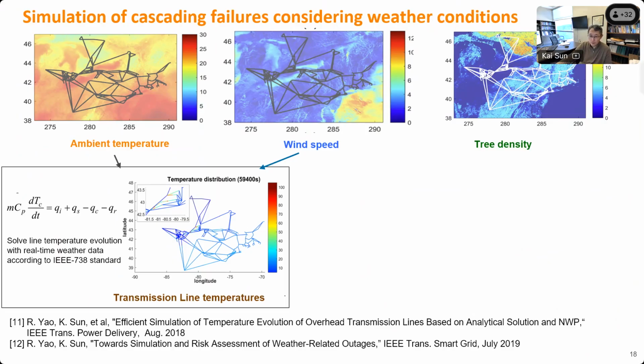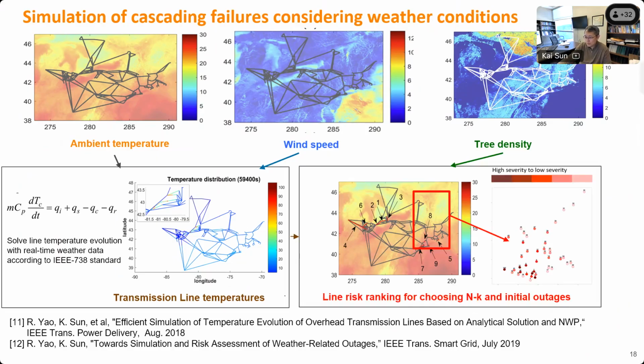For instance, you can use this standard to simulate the line temperature evolution based on the temperature and the wind speed. This tells you how the temperature will go up, and that can reduce the capacity of the transmission line. Then, comparing the capacity of the transmission line and also the tree density, you can determine the high-risk region where the cascading failure can initiate. So you can choose the N-1 contingency from that area. There are more details in those two publications.